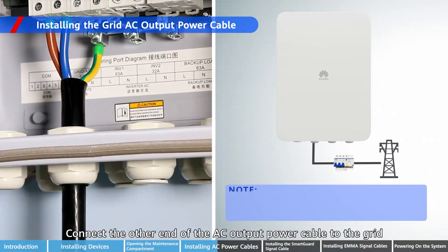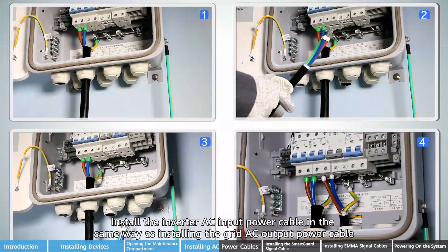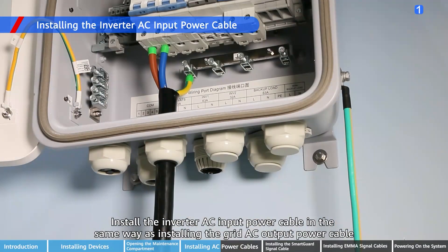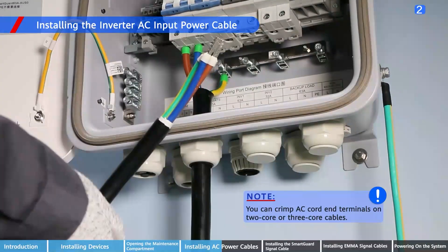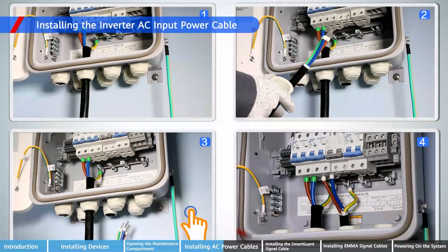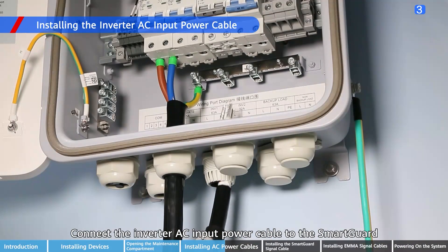Connect the other end of the AC output power cable to the grid. Install the inverter AC input power cable in the same way as installing the grid AC output power cable. Connect the inverter AC input power cable to the SmartGuard.